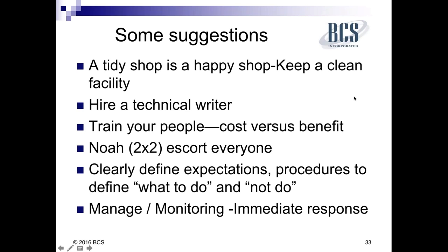Keep a clean facility. All of that dirt is working against you, especially since most of your facilities are cooled through the air or convection cooling, which means you're moving all of that dirt and contamination from under the floor, up through the raised floor panels, and then right across all the close tolerances of your equipment.